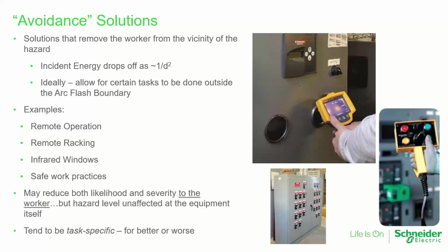And it works in a couple of ways. Incident energy drops off pretty quickly as you increase the working distance. So if we can, operate a breaker from a remote panel, or some kind of SCADA system, or even Bluetooth over your cell phone, we can do that from a distance and experience much less exposure than if you have to be standing right in front of the equipment pushing a button or whatever.